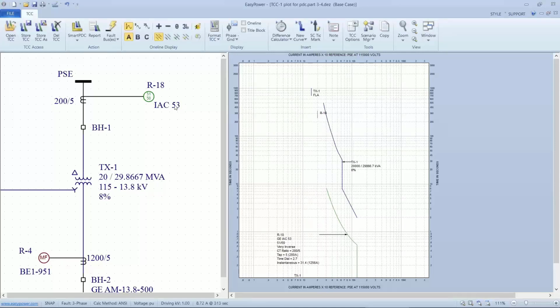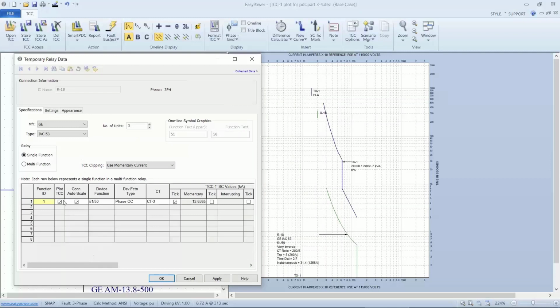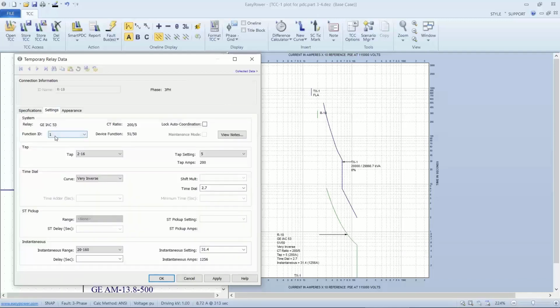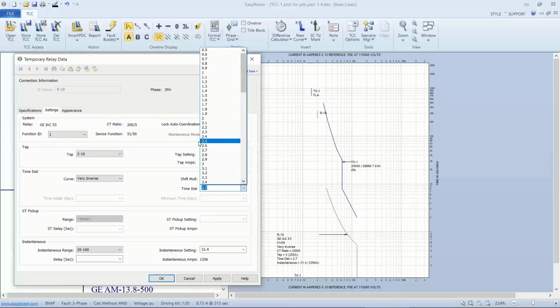Now the same adjustment will be made in the setup for the relay itself. First of all, we're plotting the TCC curves. We're showing the momentary current tick mark. If we go to settings for overcurrent pickup, we have it set at 5, which gives us this 200 amp pickup. Using 4 isn't going to give us enough bandwidth, so let's leave it at 5. Now we've selected the very inverse curve, and we've picked out some number in the medium range on the TCC plot. So let's just do 2.8.